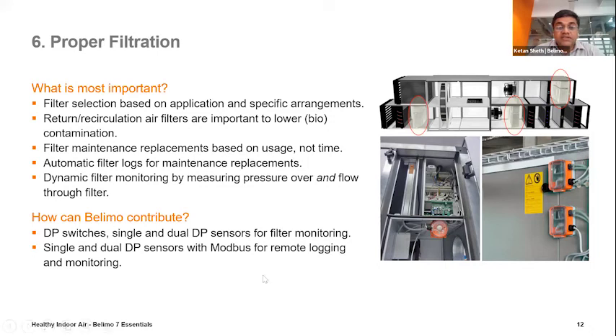Now, filter maintenance should not be on a schedule. It should be based on usage, contamination, and the dust accumulating on the filter. It should not be periodic, and automatic filter logs for maintenance and replacement are very, very essential. Another way of monitoring filter clogging is dynamic filter monitoring by measuring the pressure drop across the filter. What we provide for that is differential pressure switches, as you can see in the first picture on the right hand side, across the filter.